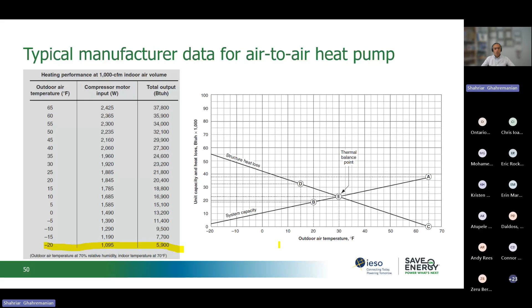So this is the temperature that we need to consider for the sizing of any heat pump for the GTA area. For the other regions of Ontario, it can be different, and we can consult the ASHRAE or Natural Resources Canada website and get those extreme weather data from there. So when they come, they look at different heat pumps for our system. Basically, they should provide us a graph similar to this.